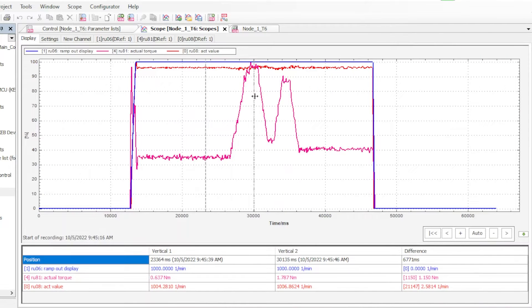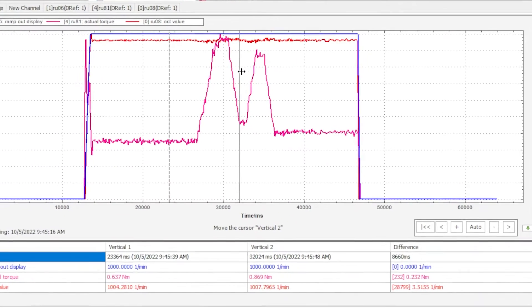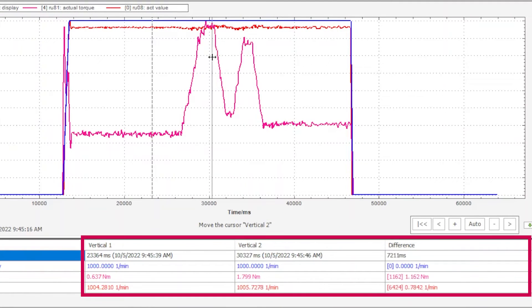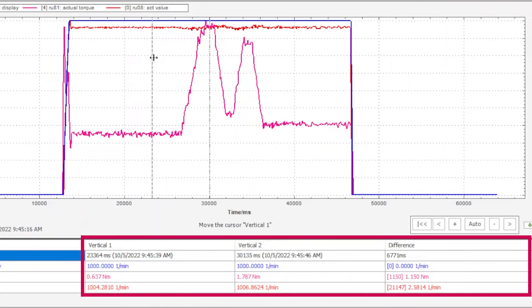COMBIVIS includes cursors to allow you to actually take measurements of the data that you just recorded. You can drag the cursors around and for example measure values like speed and torque and see how those change with each other. This is useful for troubleshooting because it lets you compare parameters against each other like commands and other parameters to see if one might be causing a fault.